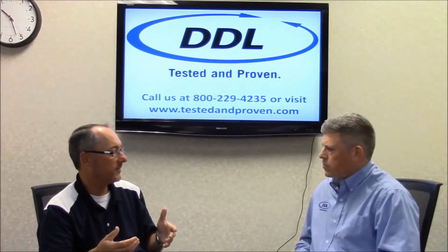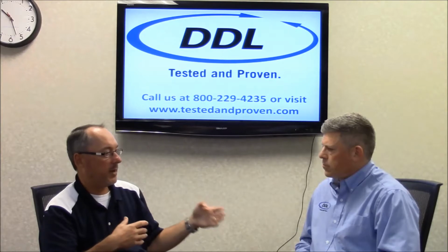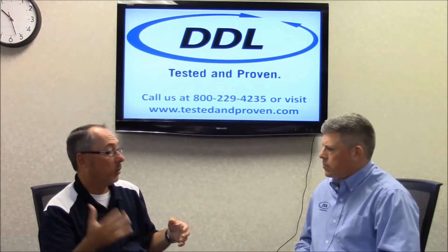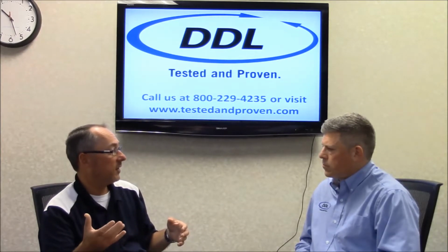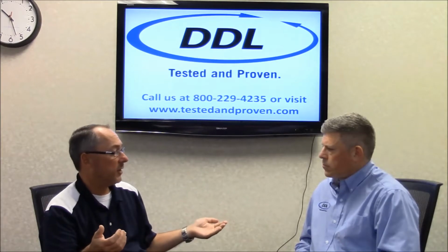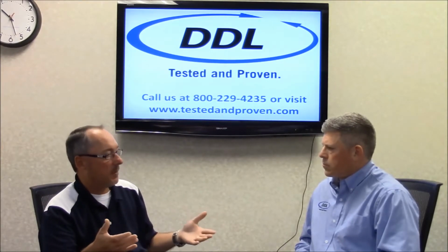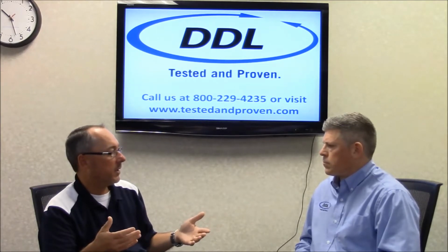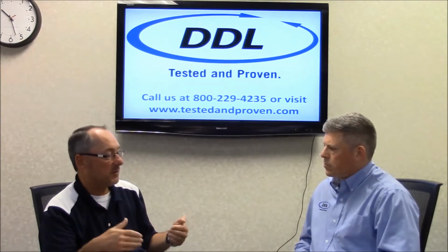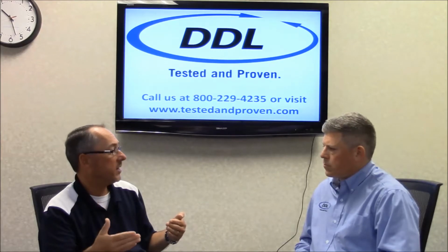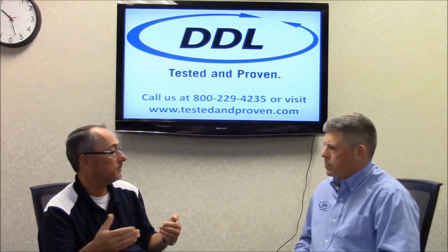Well, sure it does. So I see a lot of customers playing the game of, all right, we really truly store our stuff at 25°C, but if I use an ambient of 20°C for the aging calculation, it shortens the number of days. But ambient temperature in general is specifically related to what test temperature you use for real-time aging.